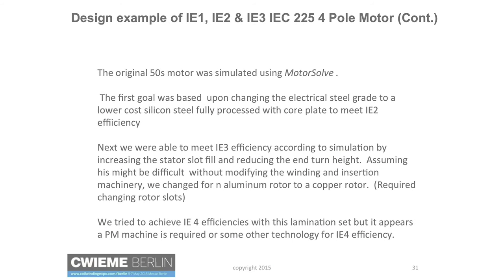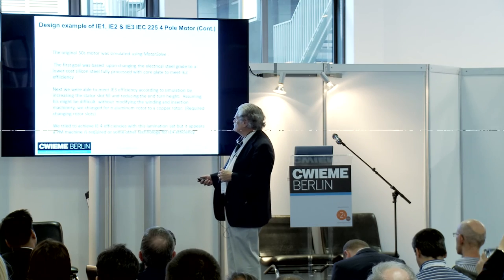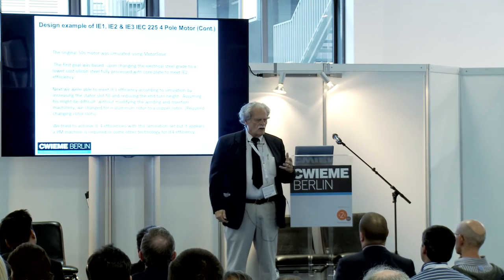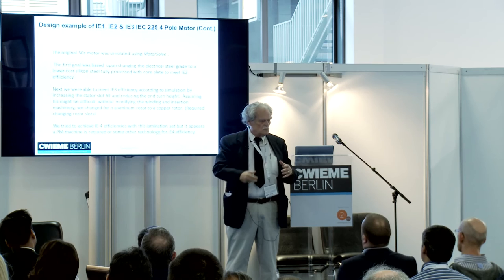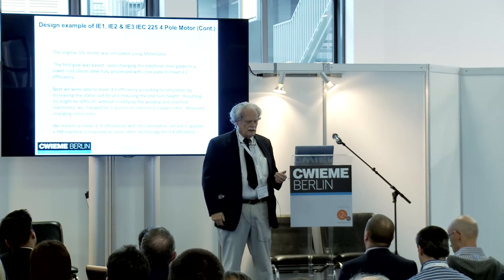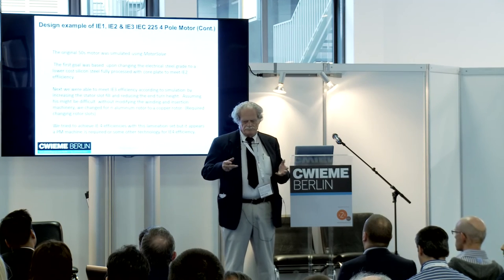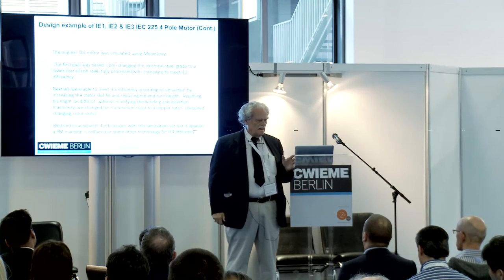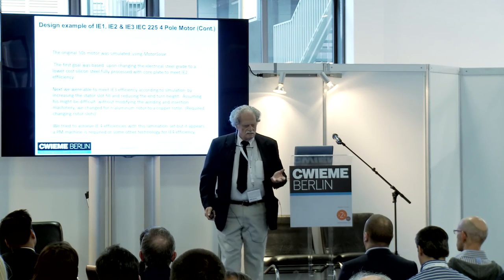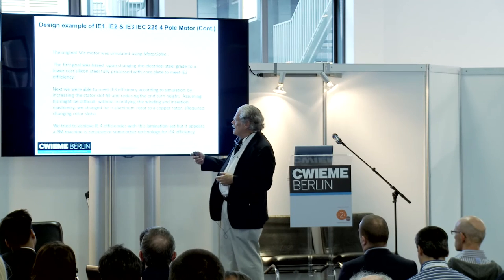But so I guess it's an advertising ploy, if nothing else. So what did we do for the meet IE2? We used lower cost silicon. We went from a very low cost commercial grade electrical steel that was very pure but didn't have silicon in it. That's what the original was. And we went to roughly a 3% silicon content steel that had, I don't know, about a third of the losses at 50, 60 hertz, something like that.